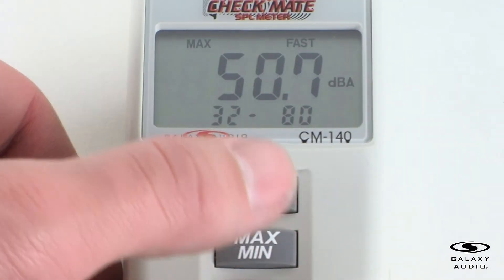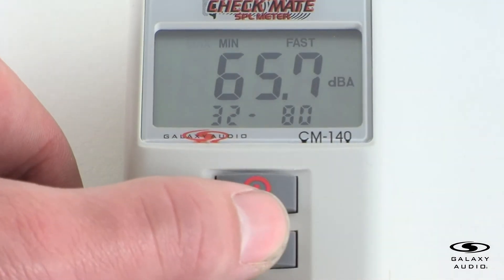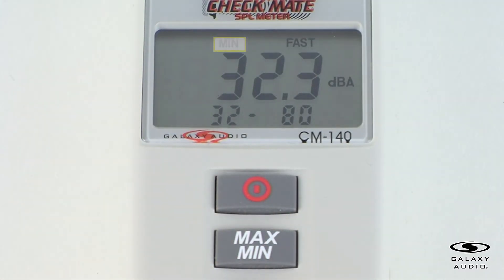Press the button once to select the max value. The CM140 will now display the maximum SPL measured. Press the button again to select the min value, which will display the minimum SPL measured.